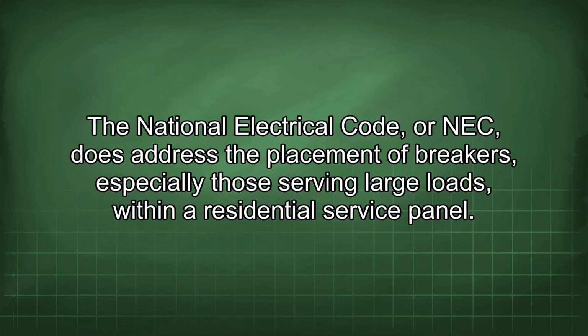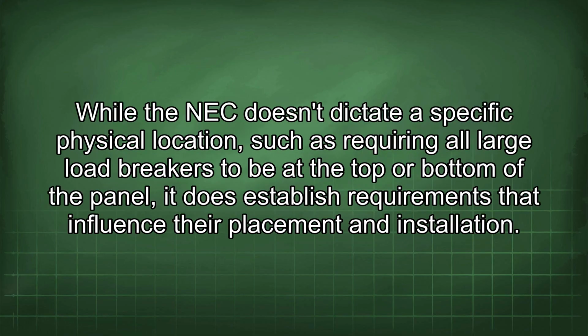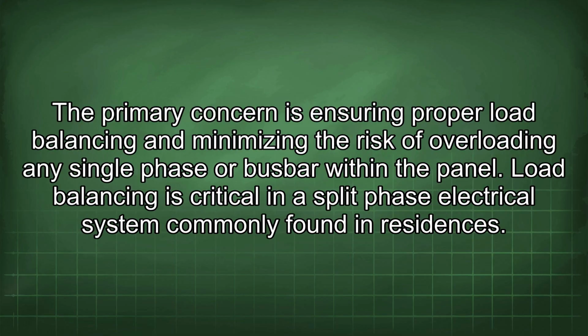The National Electrical Code, or NEC, does address the placement of breakers, especially those serving large loads, within a residential service panel. While the NEC doesn't dictate a specific physical location, such as requiring all large load breakers to be at the top or bottom of the panel, it does establish requirements that influence their placement and installation.